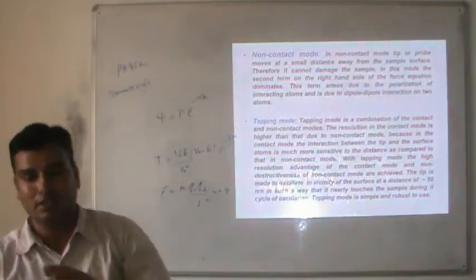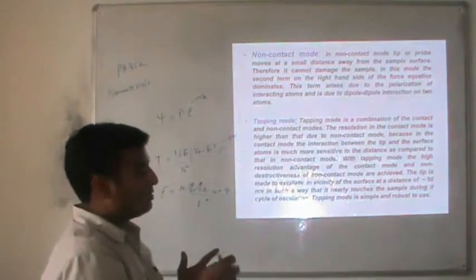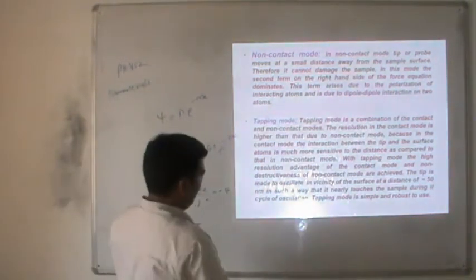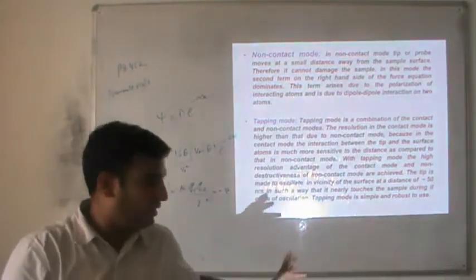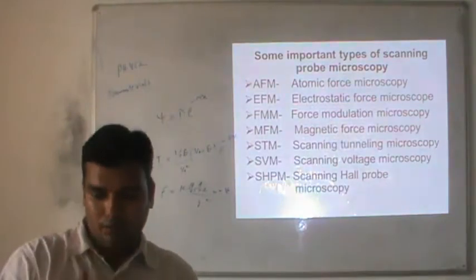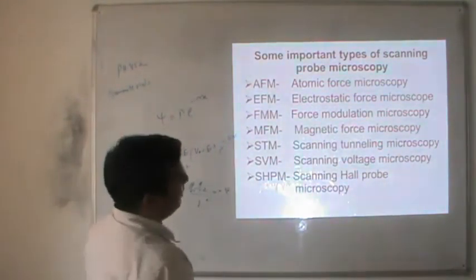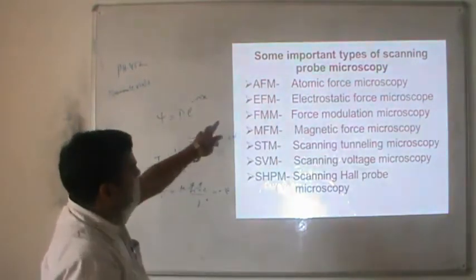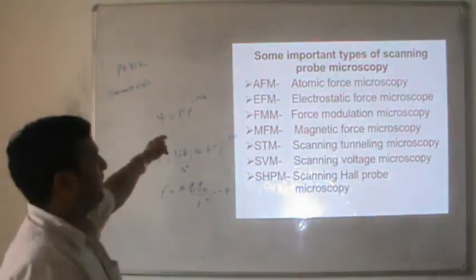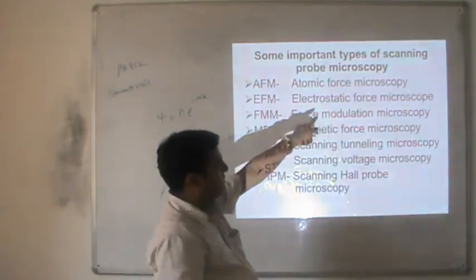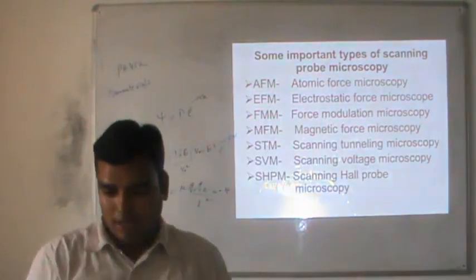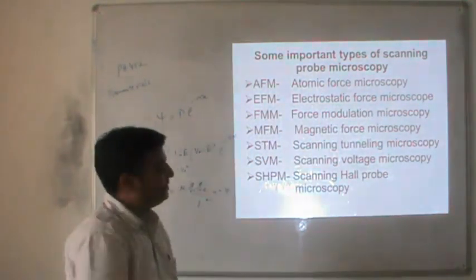In tapping mode, the tip oscillates above the surface at a distance of approximately 50 nm, nearly touching the sample during each cycle of oscillation, and it is simple and robust to use. AFM is part of a family of scanning probe microscopy techniques including atomic force microscopy, electrostatic force microscopy, force modulation microscopy, magnetic force microscopy, scanning tunneling microscopy, SVM, and SHPM. These different classifications will be discussed in the next class.